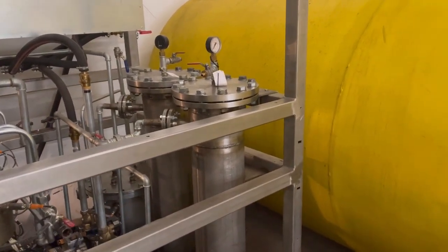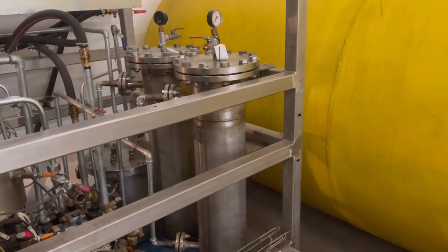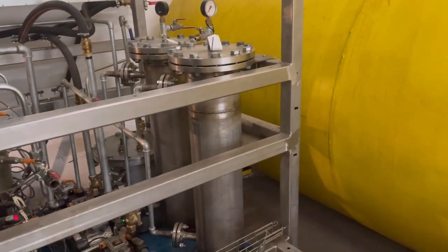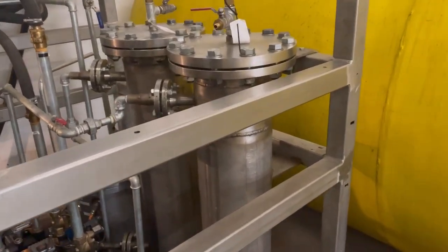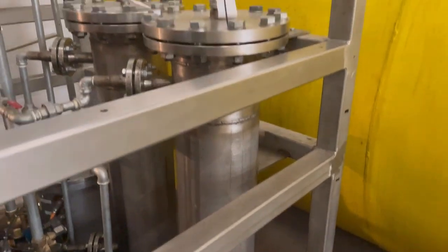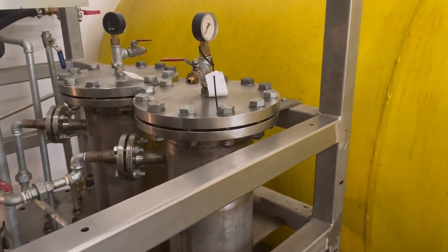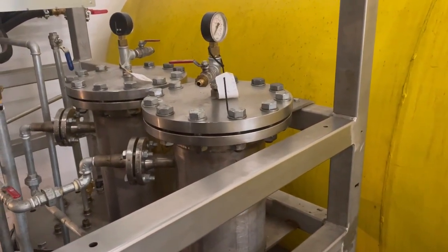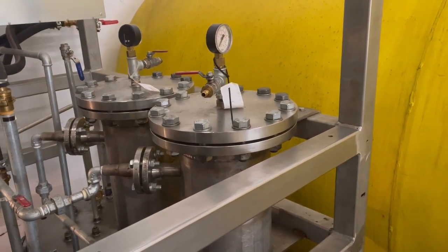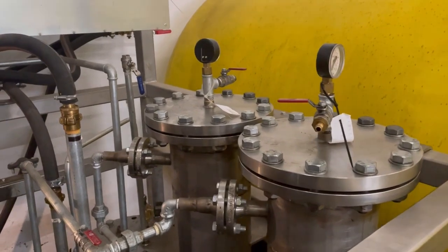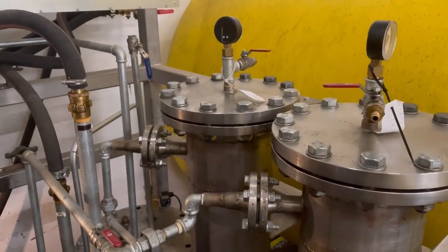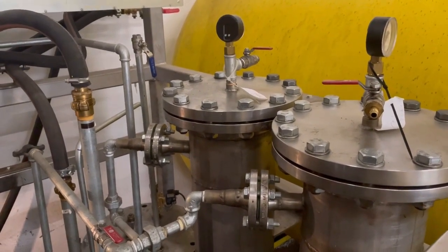We shall start by having received the product. Now it needs some form of pre-treatment, pre-cleansing. This pre-cleansing is achieved in two stages. We have stage 1, where in this column here, we basically work with a 25 micron filtration system, which is then moved into a 10 micron filtration system.